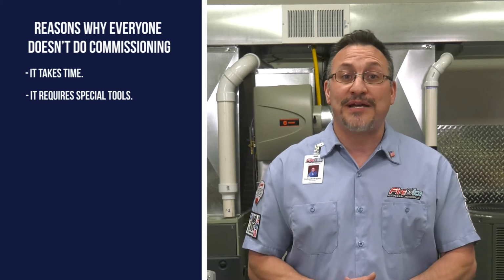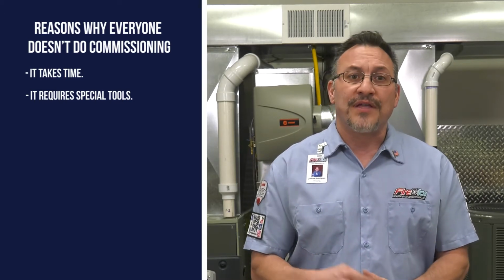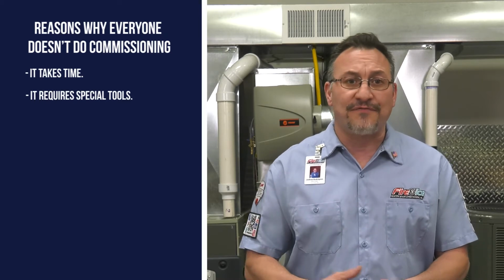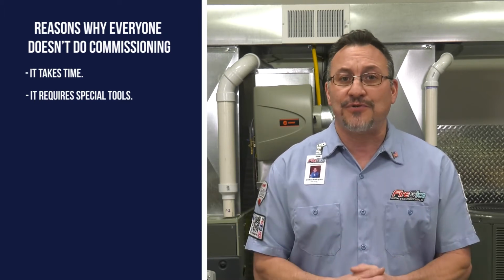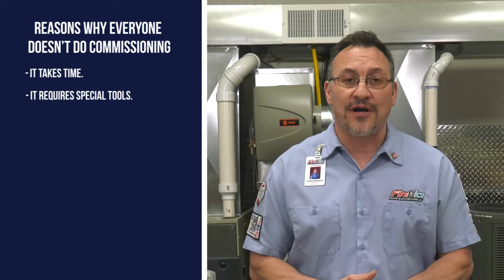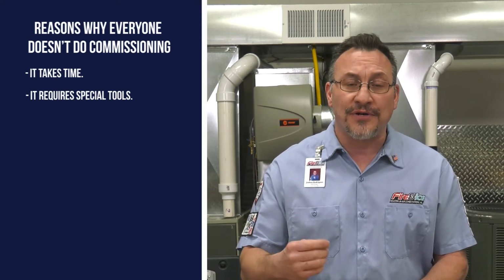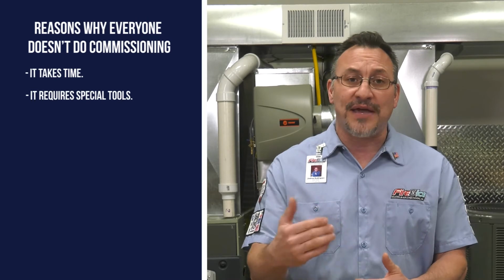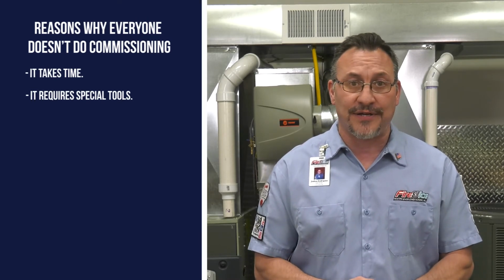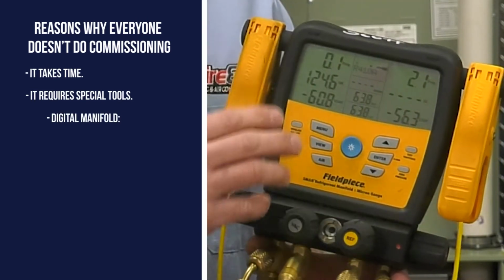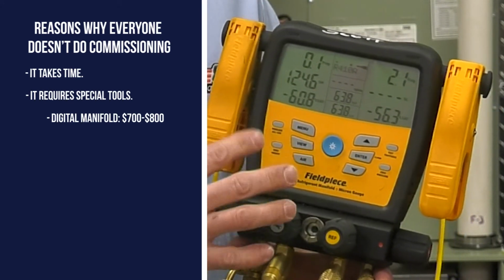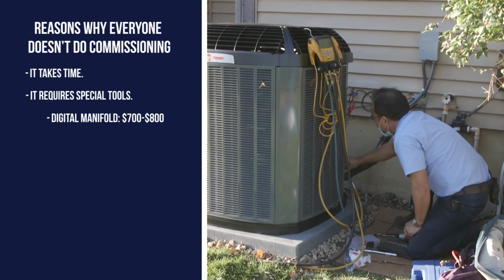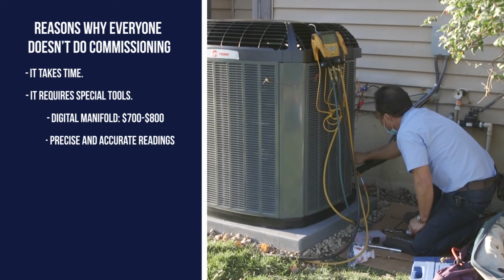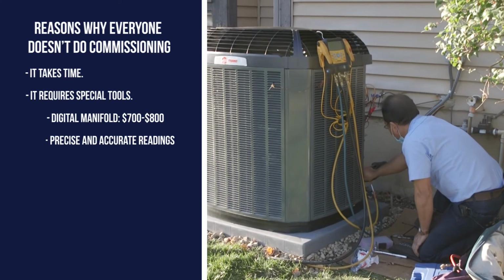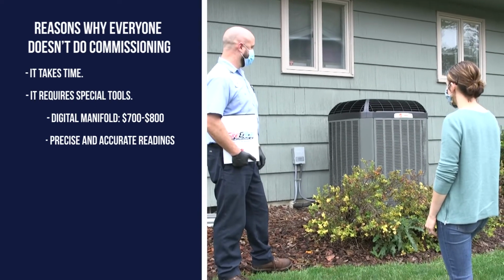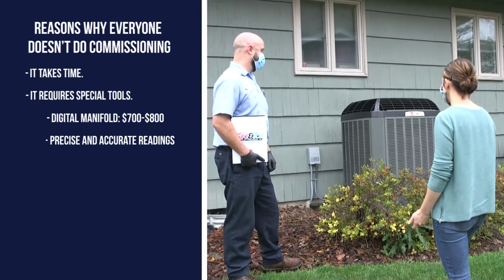It also requires special tools - multiple tools like digital gauges, manifolds, and meters, everything we showed you earlier - to perform this commissioning process properly and record the actual data required to make sure the equipment is running properly. This digital manifold set with hoses retails anywhere between $700 and $800. It gives very precise readings to properly set up and commission your new equipment, giving you the best chance for the best performance and the most energy savings you deserve.